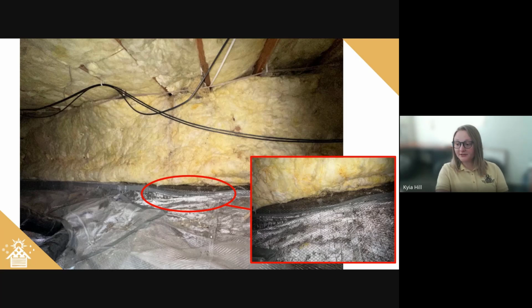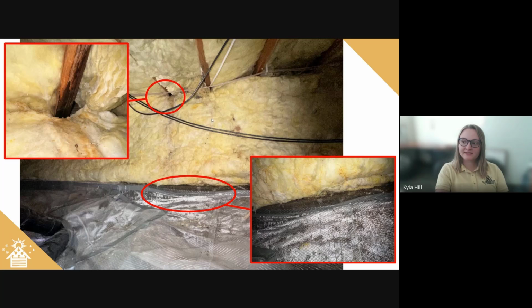There wasn't any water on top of the vapor barrier, so all of this humidity shows the vapor barrier is working and blocking that humidity from further coming up. But if you were to continue to zoom in, this is where the issue is. It's at the very top.